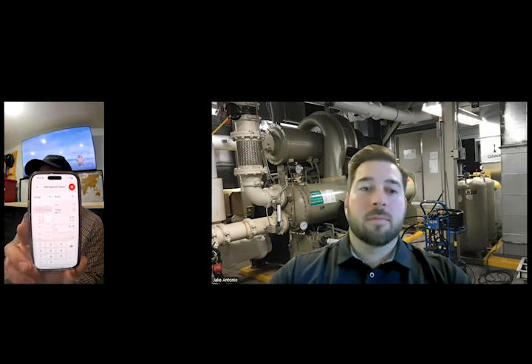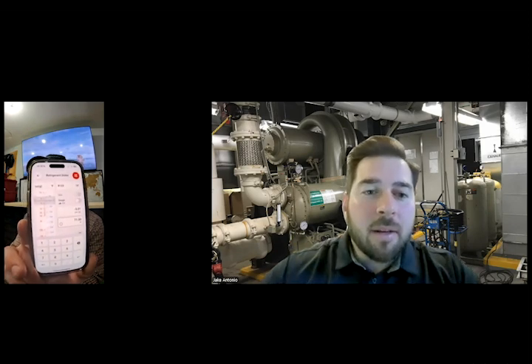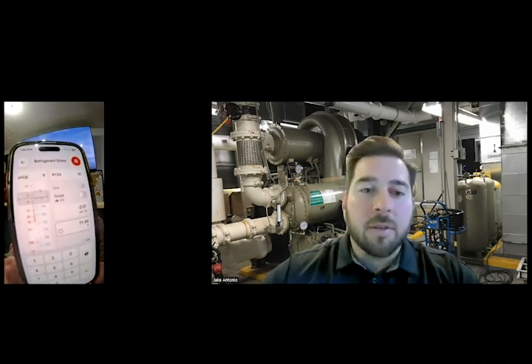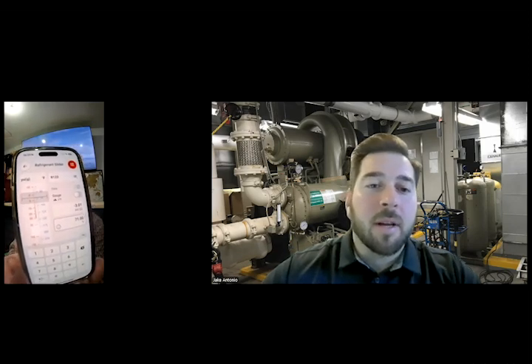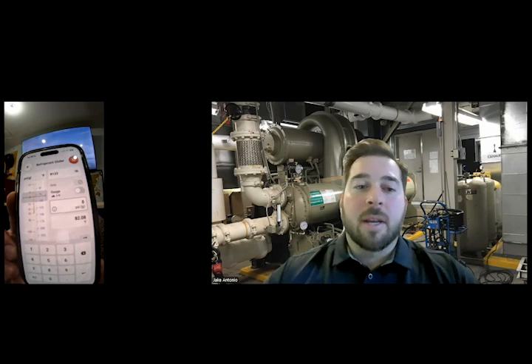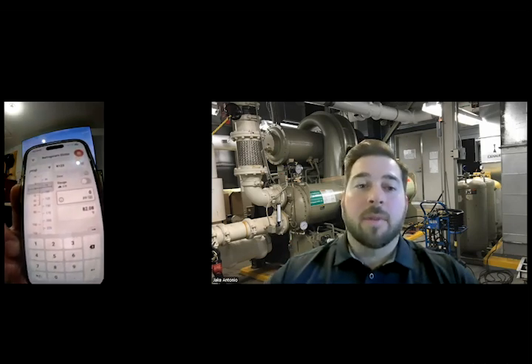Jake talked about R123 - I just checked it out on the Danfoss app, the one you can look at pressure-temperature values for. I believe at about 75 degrees Fahrenheit it's 0 psi, let me check - 82 Fahrenheit, zero psig. So if you were in this chiller plant and it was 82 degrees, you could have these bottles open to the atmosphere and it's at 0 psig. This refrigerant is mostly in a vacuum, because room temperature is about 70 to 75. These chillers actually run in a vacuum on the low side, and on the high side they do tend to get to positive pressure, but they consider this a low pressure chiller based on the refrigerant R123. That's pretty cool.